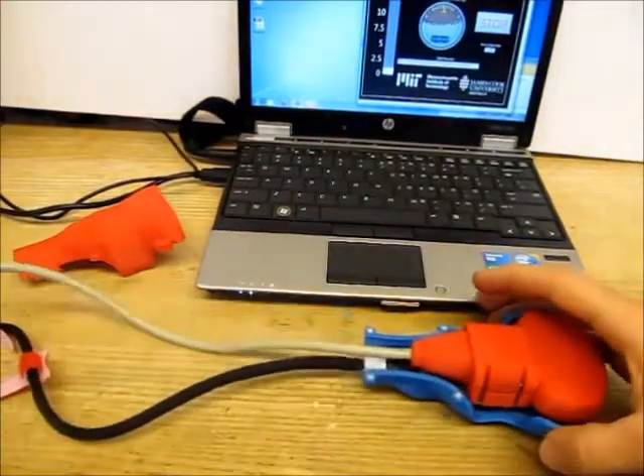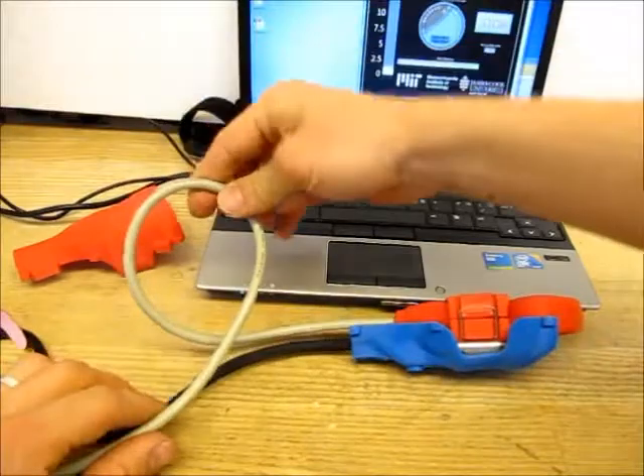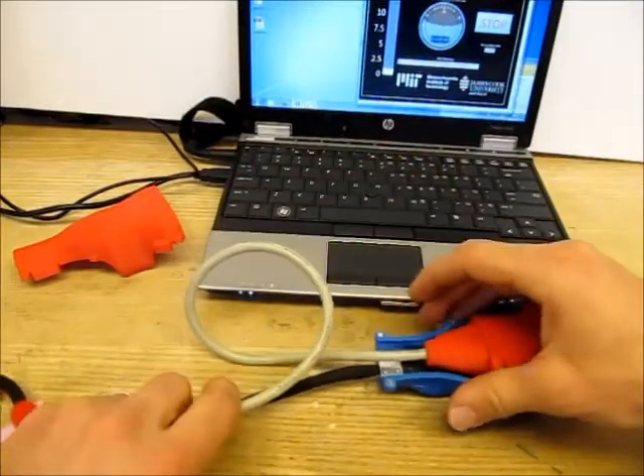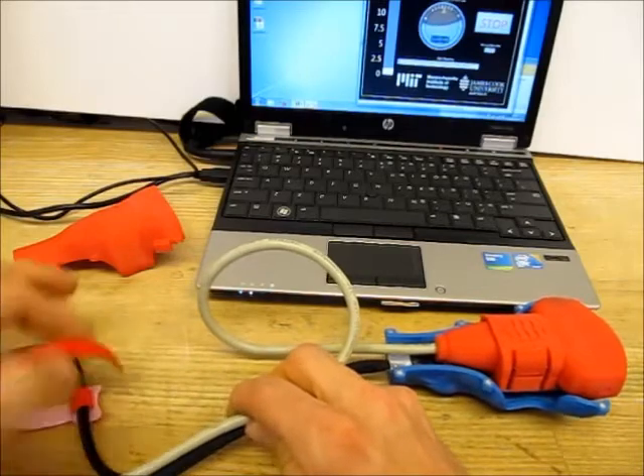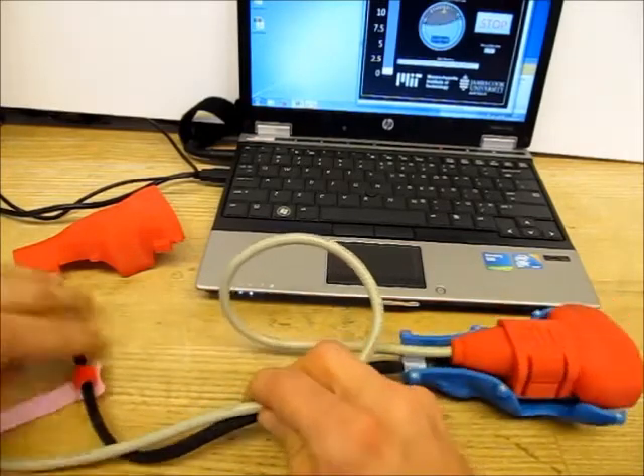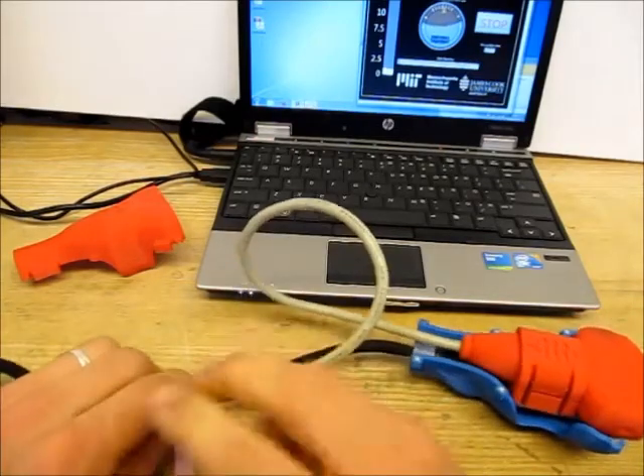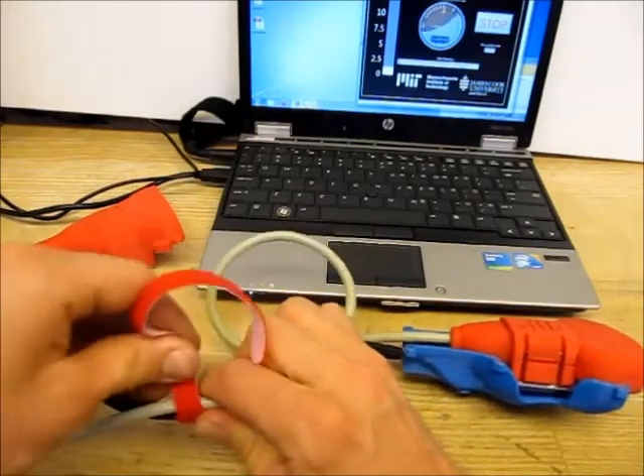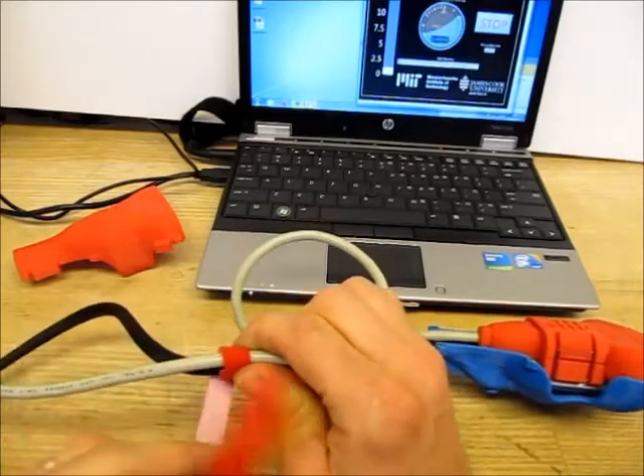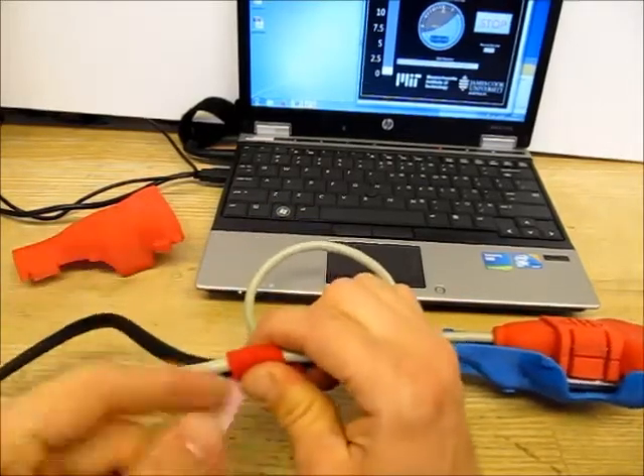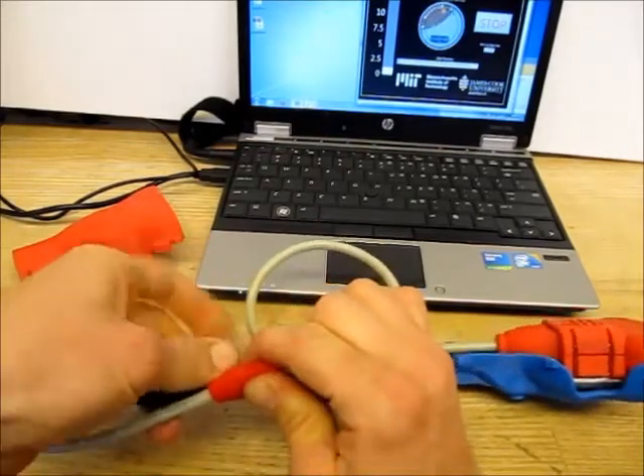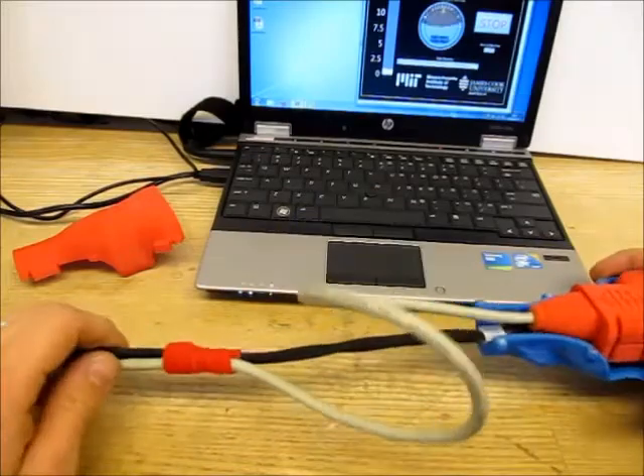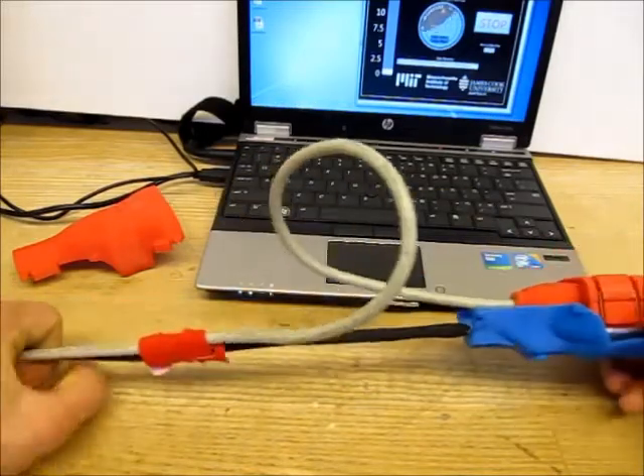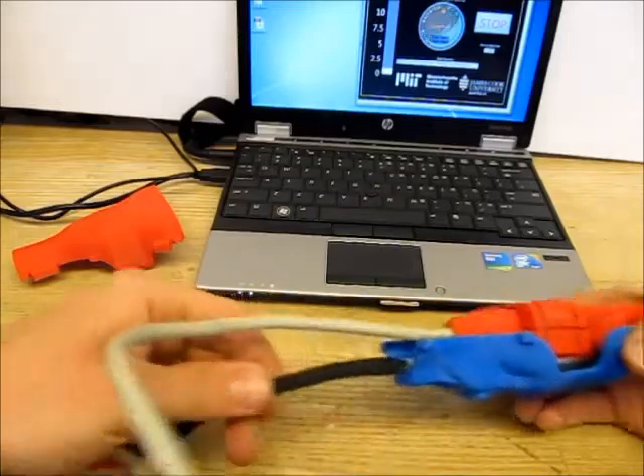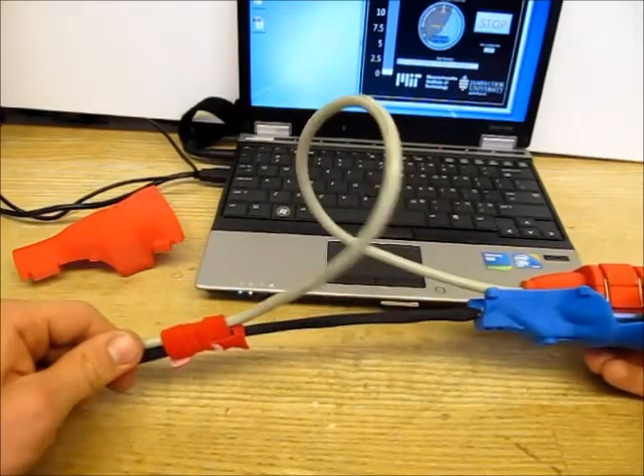Now, in order to strain relieve the ultrasound cable, what we first want to do is create a little loop. It's a little loop that's about this big. Next, we take our Velcro, this Velcro strip that should be attached to the black device cable, and we take that Velcro and we wrap it very tightly around the ultrasound cable. So now, any tension that's applied to the system will go through this black device cable, which is capable of supporting the tension, and it won't go through the ultrasound cable.